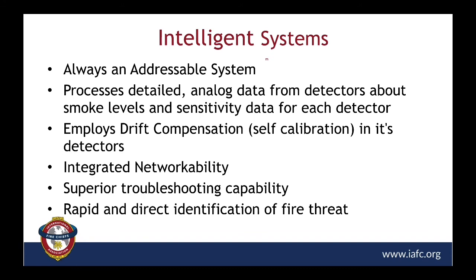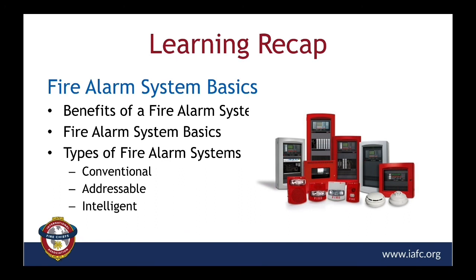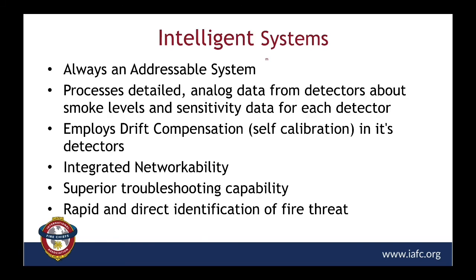And they give the owner, they give yourself if you request it, and certainly the fire alarm technician, a printout of the status of every smoke detector in the building, letting them know if it's getting dirty or maybe wearing out and needs to be replaced. So it's just that sharing of technology that moves forward. They also have what they call drift compensation, where these detectors are looking at the atmosphere in a room and adjusting to the fact that we may suddenly be doing some cooking in a space, or some kind of processing where the atmosphere and the level of air movement is different. These things will self-adjust to that.